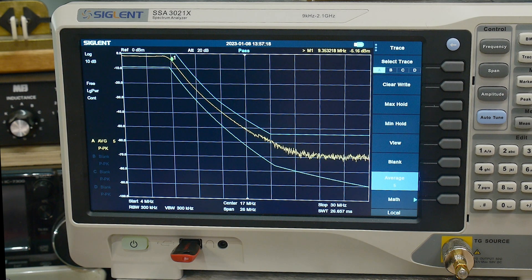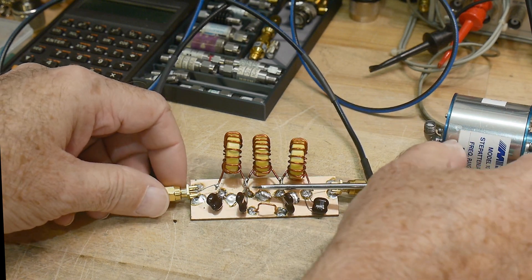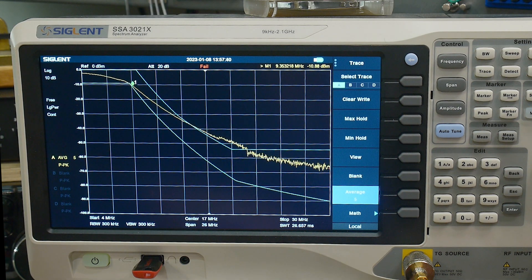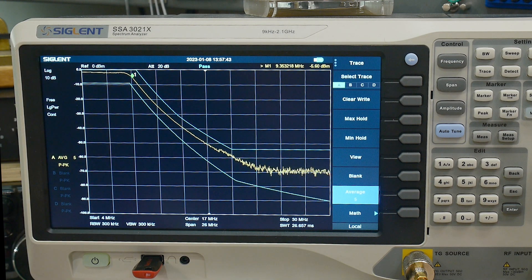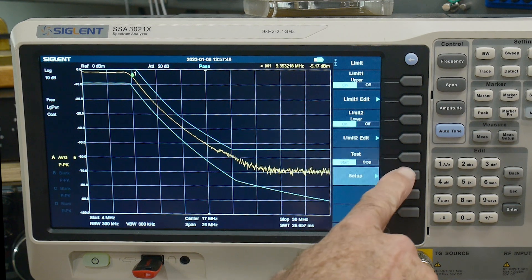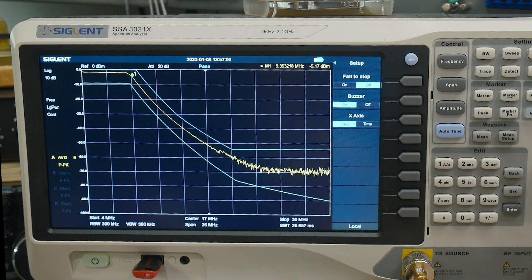If the curve goes below or above the limits, it will fail. I'm going to pretend there's a short between these two — you can hear that it's giving me a warning that there was some kind of problem. I'll create a short on screen here, and you can see we're starting to go outside of the bounds and getting a sound. You can turn that sound on and off by pushing limits, going into setup, and setting buzzer on or off.